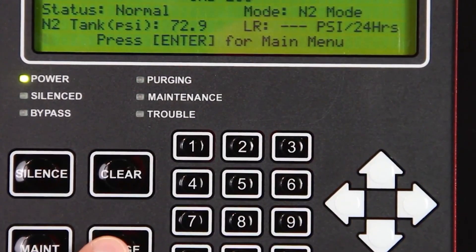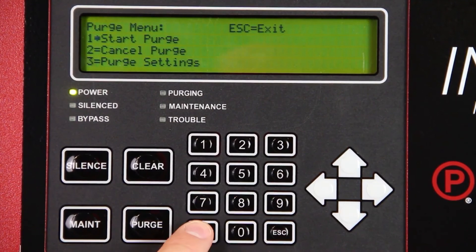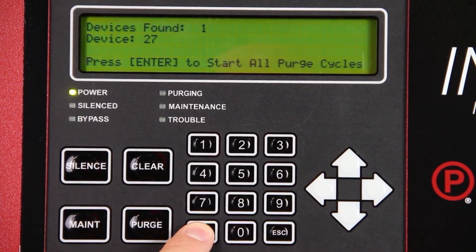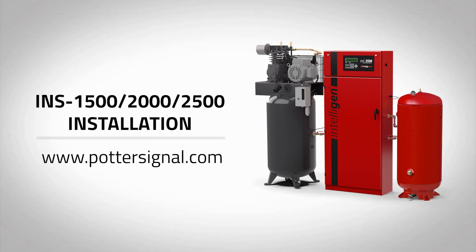If an INSPV is connected to the generator and you have learned the network, press the Purge button on the IntelliGen display keypad. Enter 0000. Press Start Purge. Select All Devices and press Enter. The system is now purging. If an NGPSPV mechanical purge valve is being used, simply remove the brass plug and open the ball valve. This completes the installation for Potter's INS1500, 2000, and 2500 nitrogen generator.